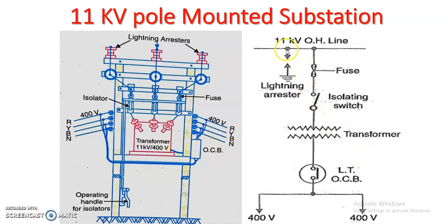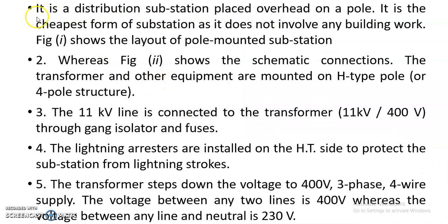So in the single line diagram we can see the symbol of the lightning arrestor, then the fuse, isolating switch, then the transformer, LT oil circuit breaker, then the 400 volt supply. So this is our 11 kV pole mounted substation. It is a distribution substation which is placed overhead on a pole. It is the cheapest form of substation as it does not involve any building works.